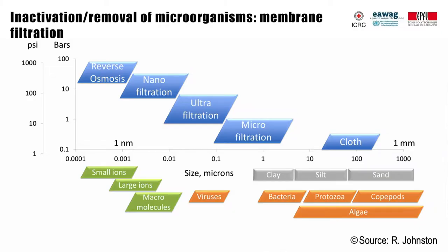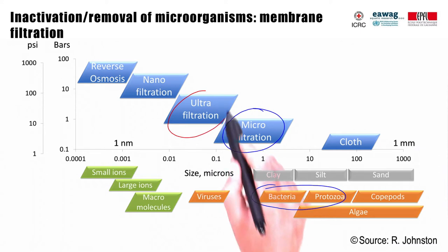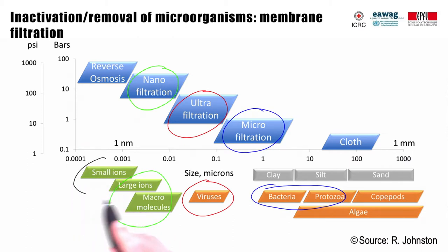During membrane filtration, water is driven by a pressure difference between the feed water and filtrate through a filter with pores of a defined size range. Usually polymeric membranes, or sometimes ceramic membranes, are used. Microfiltration has pores in the size range of bacteria and removes them and particulate matter by size exclusion. Ultrafiltration membranes are tighter and also remove viruses, which are 20 to 80 nm in size. Nanofiltration requires considerably higher pressure as the pores are smaller, but is capable of retaining macromolecules and larger ions. Small ions such as salt ions can be removed by reverse osmosis, requiring even higher pressure.